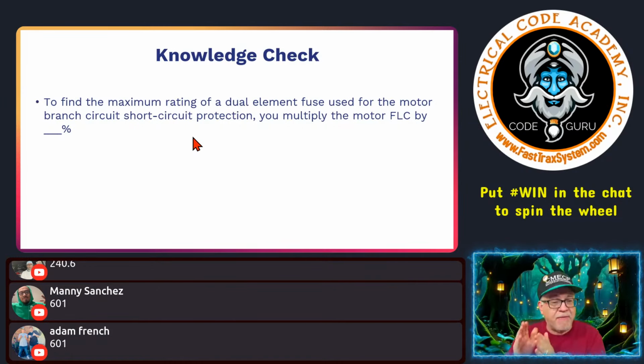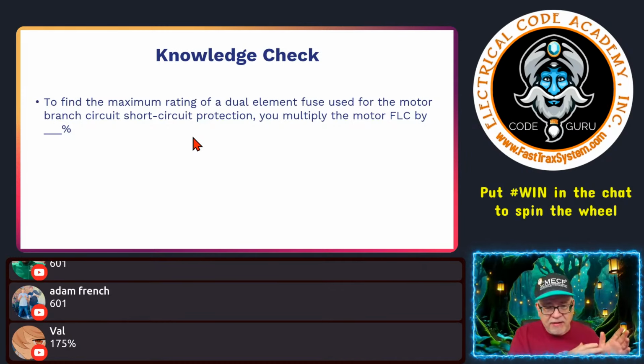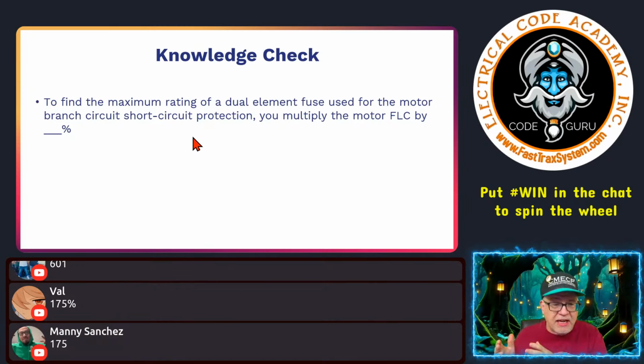That's where you're getting the FLC, as opposed to the nameplate, which is like the FLA. The nameplate's amps are based on other factors like all of the conditions and the efficiency of the motor and all that kind of stuff, whereas the FLC, which is in the code, is a hard number. That's so that if you replace a motor of that size, you're typically going to be a little conservative by using the FLC for sizing conductors, short circuit ground fault protection, things like that, right? So that's why they do it.